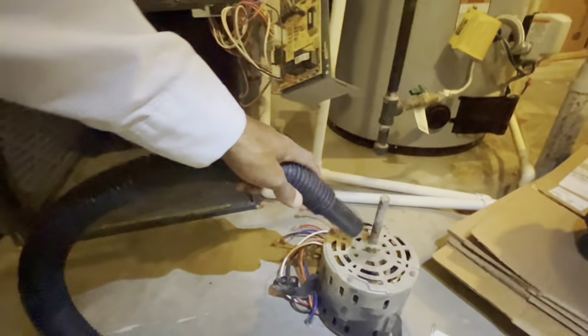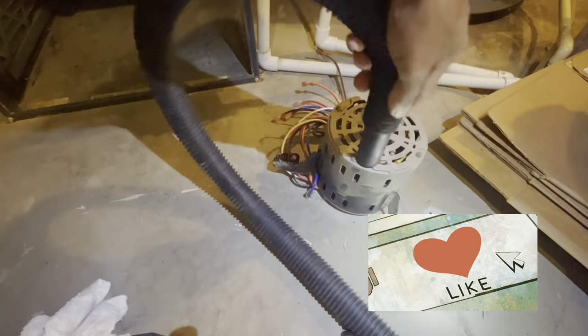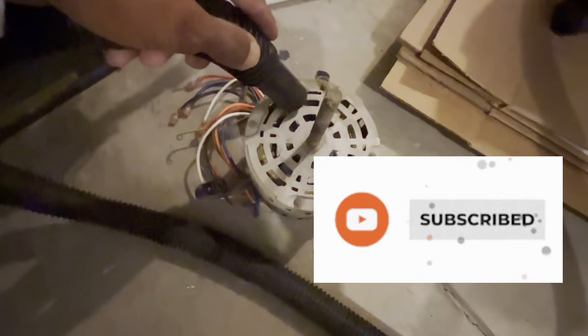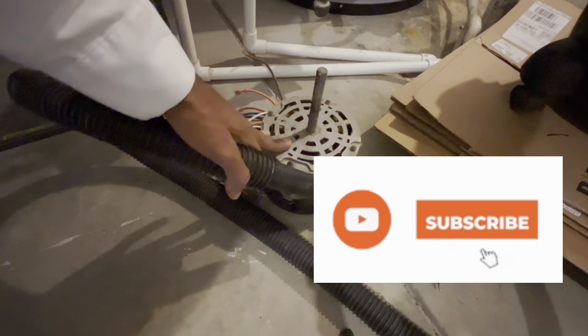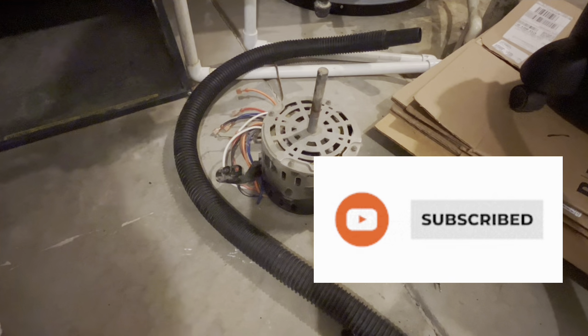So right now I'm taking that shop vac and getting all the dirt and debris off of it as much as possible. The client was not there at the time to approve any kind of recommendations or anything like that. I was just there to do a cleaning and check. So that's the service that I'm providing here, getting everything as clean as possible and putting everything in a report. And then I'm going to call the customer and let them know exactly what's going on with the condition of the furnace that they have, because they were selling the home.